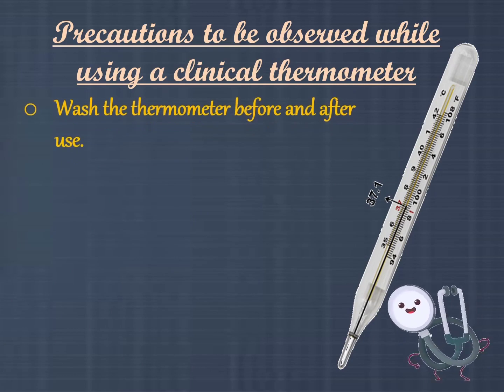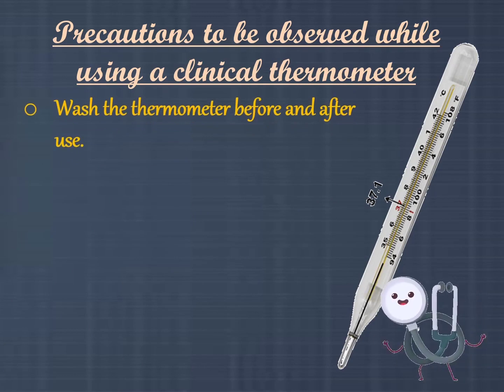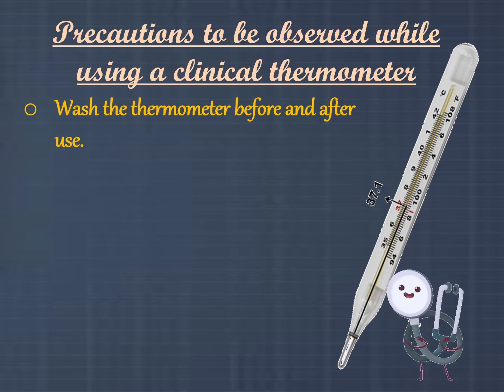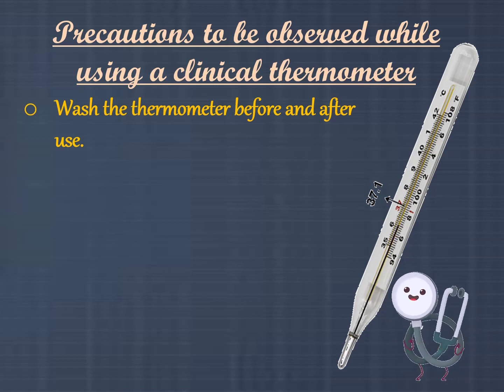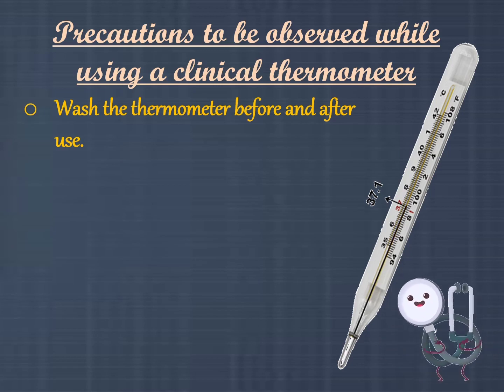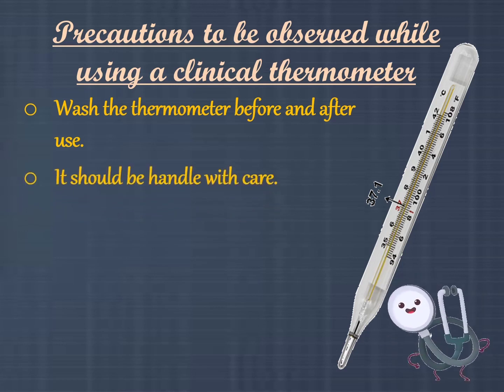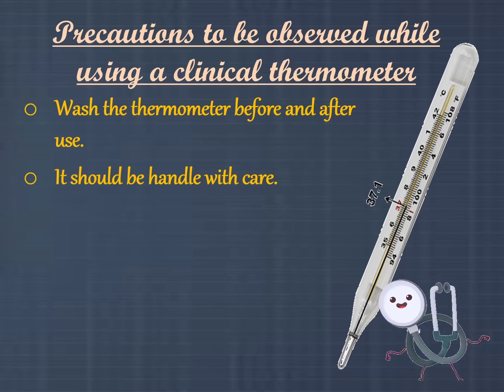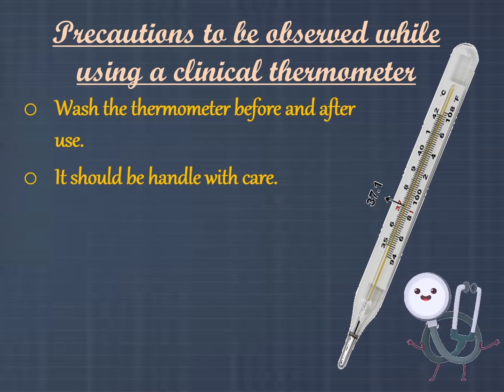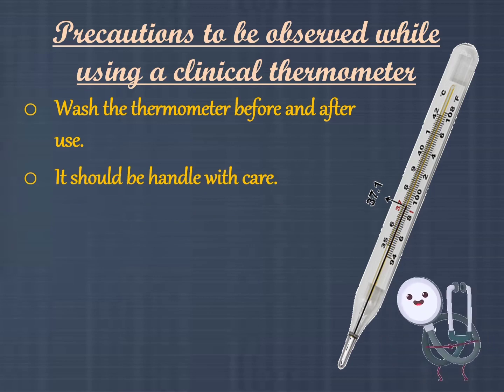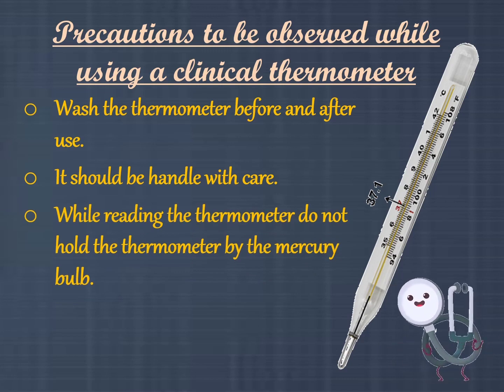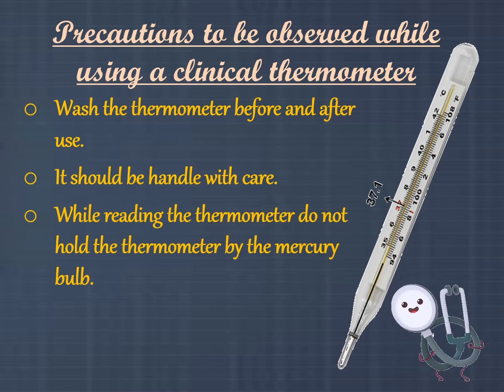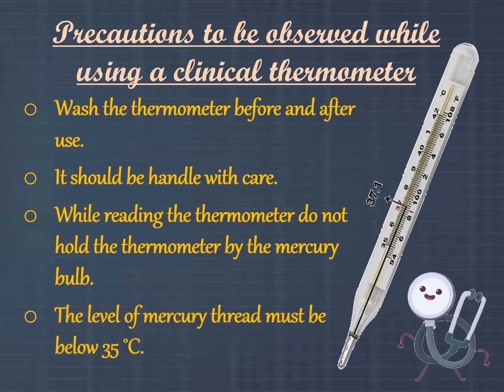Precautions to be observed while using a clinical thermometer: Number 1, wash the thermometer before and after use, preferably with an antiseptic solution, and dry it using a cotton swab. Number 2, it should be handled with care — if it hits against a hard object, it can break. Number 3, while reading the thermometer, do not hold it by the mercury bulb. Number 4, the level of mercury thread must be below 35 degrees Celsius before use.